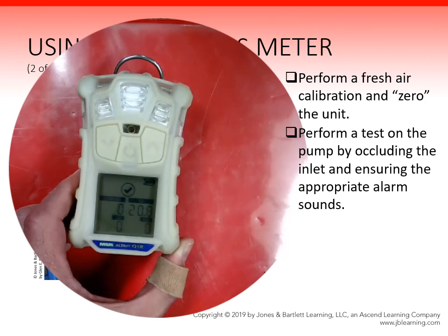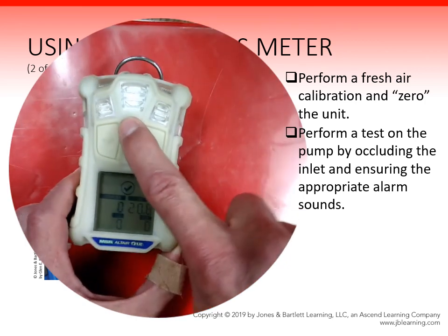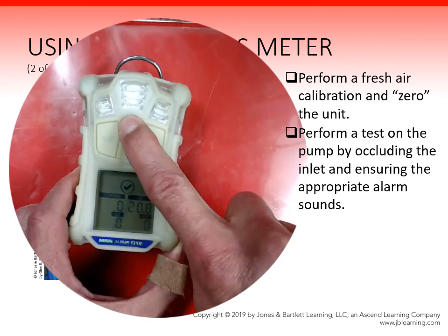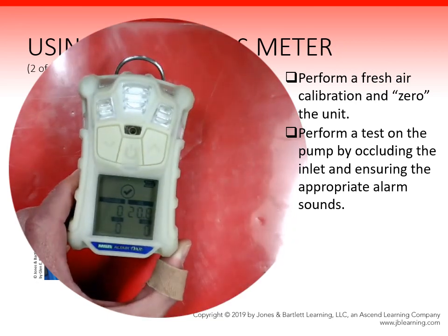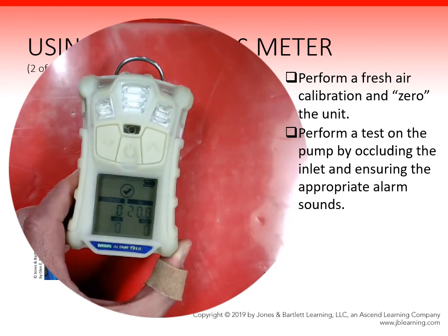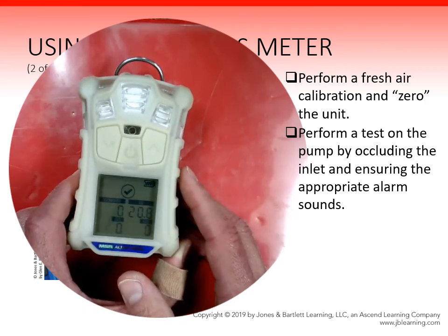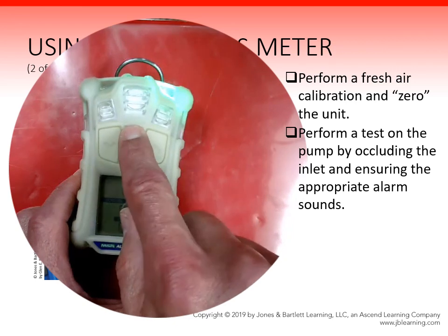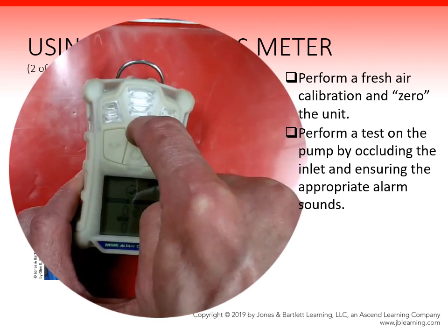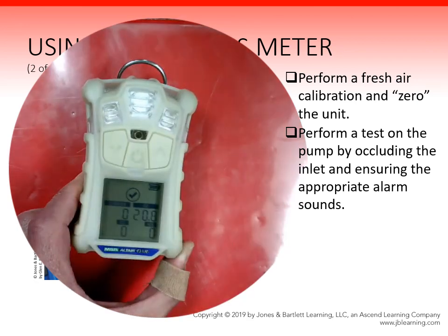So what you can also do on some of these, as I mentioned in the lecture portion, is that you can do an occlusion test by covering over that fresh air intakes, the air intake inlet. On some models of 4-gas meters, that will trigger a clogged response, and the meter will give you an alarm. On our specific meters, it's designed to resist clogging and it won't let you manually occlude that inlet. So you won't be able to do a fresh air inlet occlusion.